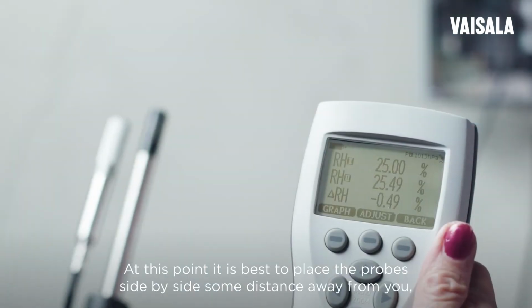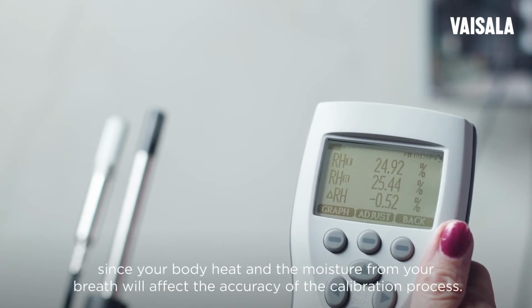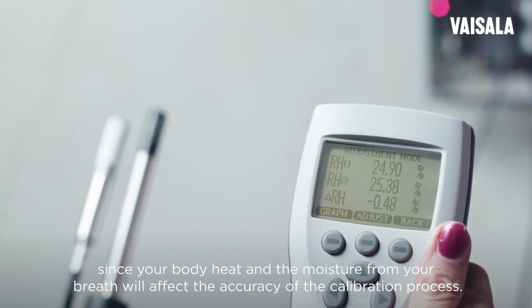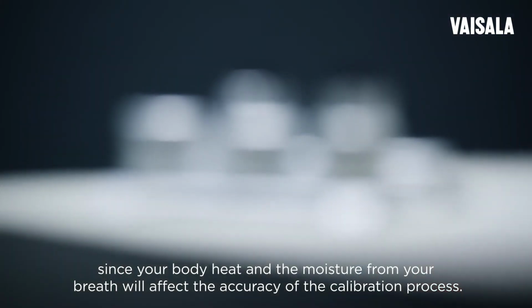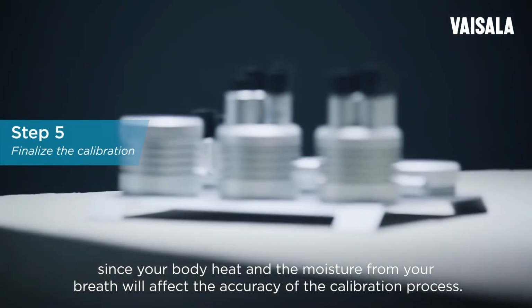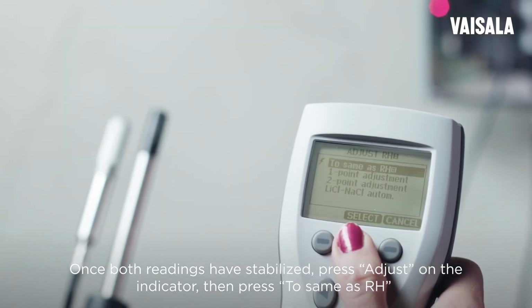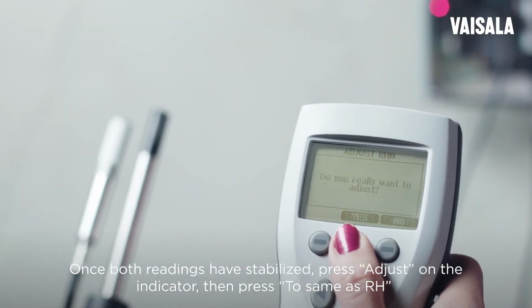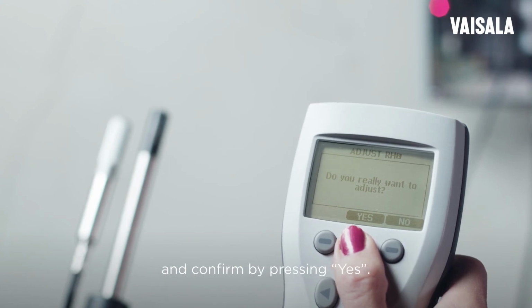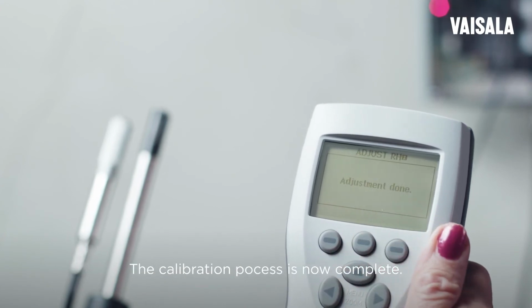At this point, it's best to place the probe side by side some distance away from you, since your body heat and the moisture from your breath will affect the accuracy of the calibration process. Once both readings have stabilized, press Adjust on the indicator, then press to same as RH and confirm by pressing Yes. The calibration process is now complete.